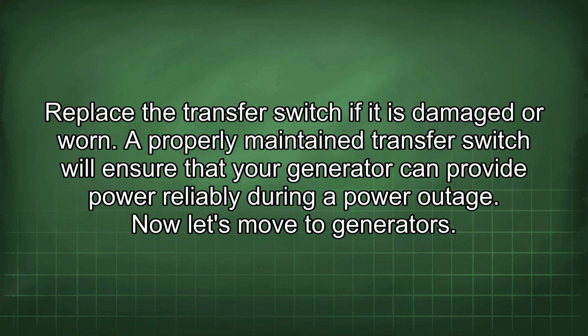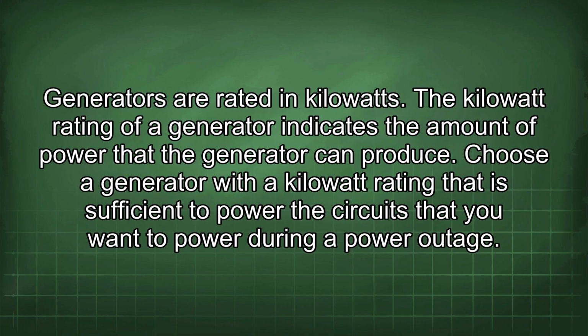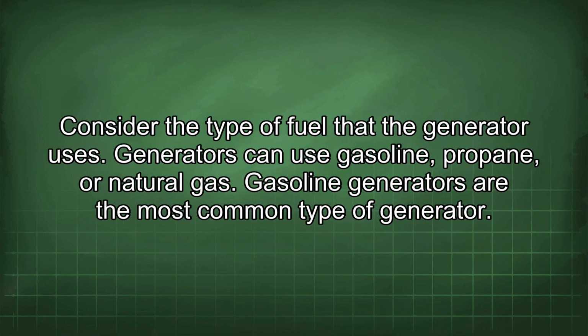Now let's move to generators. Generators are rated in kilowatts. The kilowatt rating of a generator indicates the amount of power that the generator can produce. Choose a generator with a kilowatt rating that is sufficient to power the circuits that you want to power during a power outage. Consider the type of fuel that the generator uses.